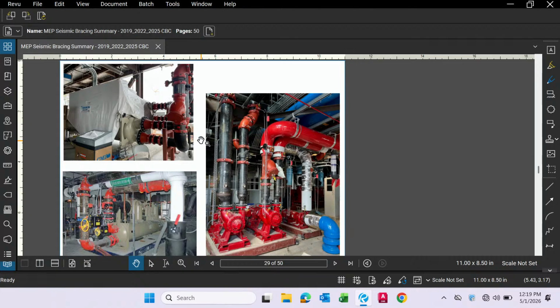This piece of equipment, this chiller, is sitting on spring isolators. During a seismic event, especially when equipment is mounted on spring isolators, they move a lot due to the presence of the isolators. These flexible couplings are rigid, and they prevent that type of movement, so they still induce a lot of stress on the pipe connection into the equipment. In this particular job, these couplers were specified, so the contractor just used them.